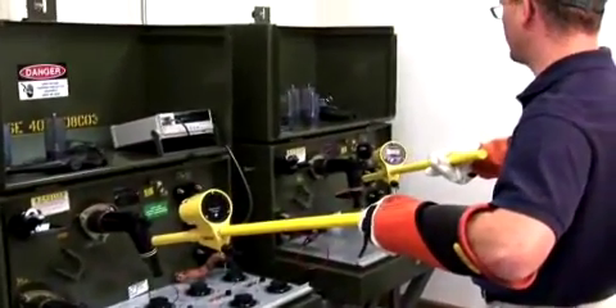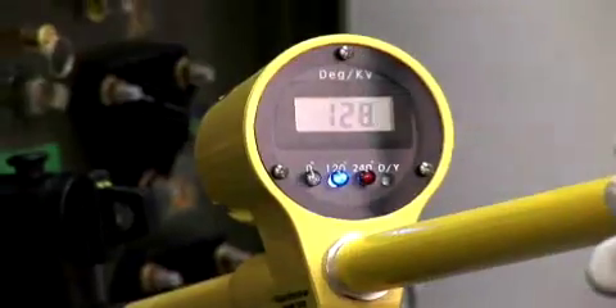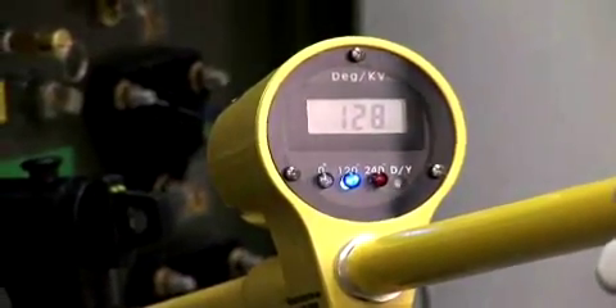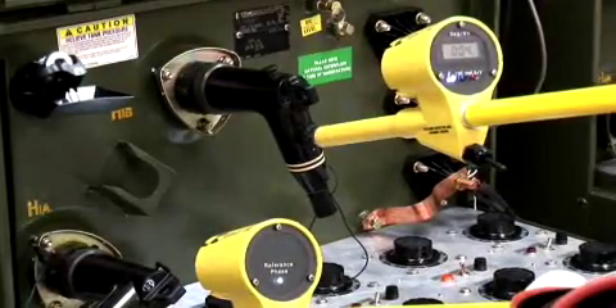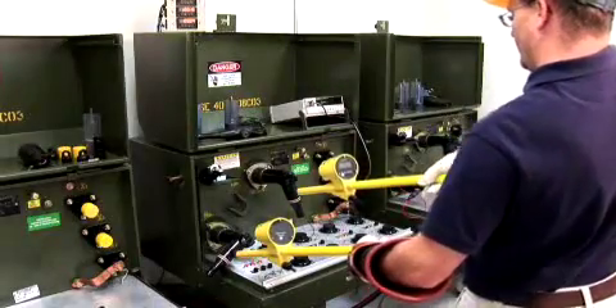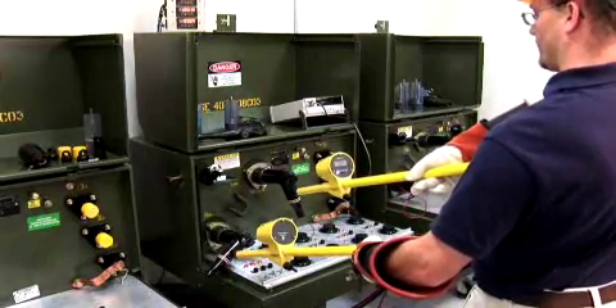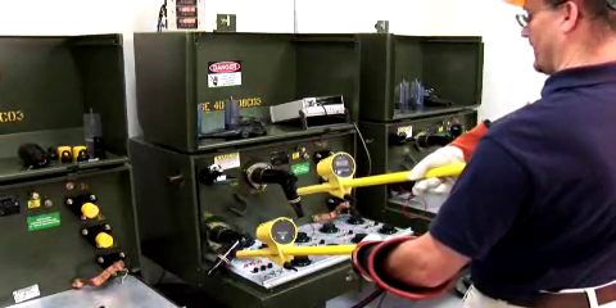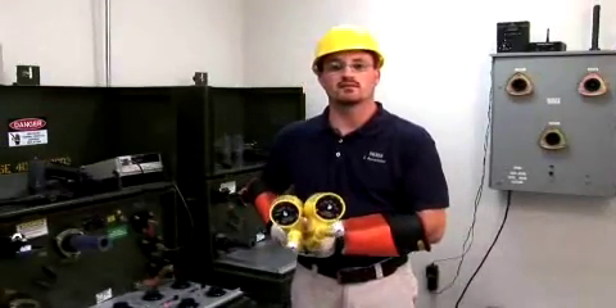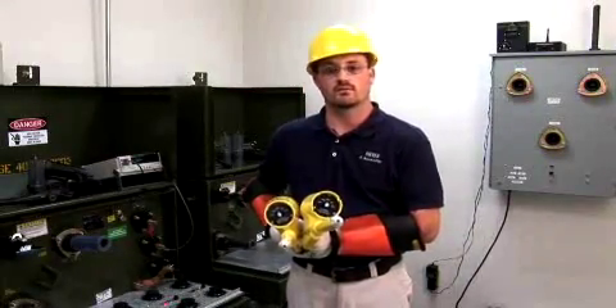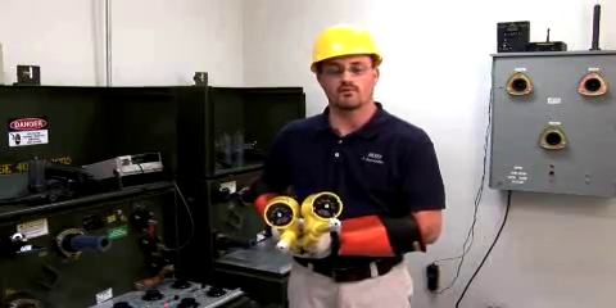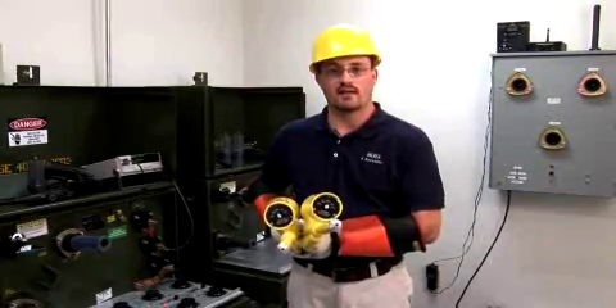Now we can begin to phase. We have a white light and a blue light. We're measuring approximately 120 degrees. And now we're measuring two test points. We got a white light. We're measuring approximately 4 degrees. So that indicates that these two are in phase. We have the PD800W phasing tool. It also serves as a voltage detector for all primary from 4 kV to 69 kV.